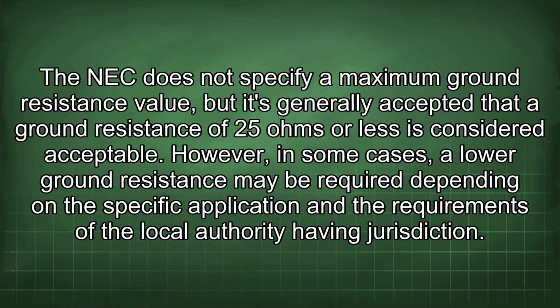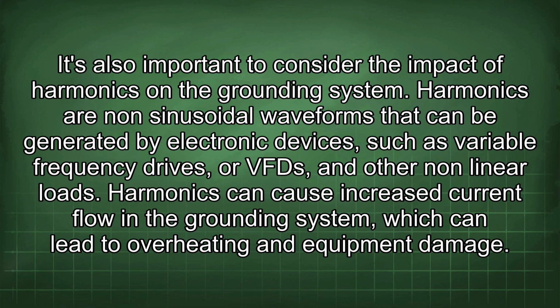The NEC does not specify a maximum ground resistance value, but it's generally accepted that a ground resistance of 25 ohms or less is considered acceptable. However, in some cases, a lower ground resistance may be required depending on the specific application and the requirements of the local authority having jurisdiction. It's also important to consider the impact of harmonics in the grounding system. Harmonics are non-sinusoidal waveforms that can be generated by electronic devices, such as variable frequency drives, or VFDs, and other nonlinear loads. Harmonics can cause increased current flow in the grounding system, which can lead to overheating and equipment damage.